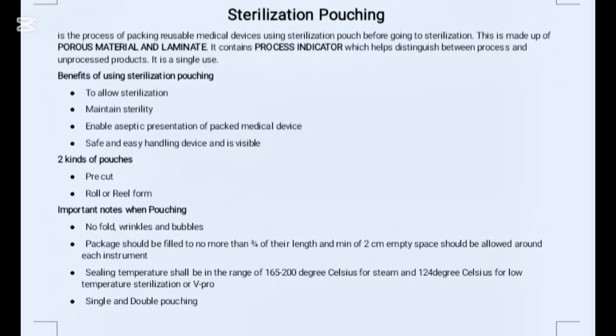Sterilization pouching is the process of packing reusable medical devices using a sterilization pouch before going to a sterilizer. This is made up of porous material and laminate. It contains process indicator which helps distinguish between processed and unprocessed products. This is single use, or we call it disposable.